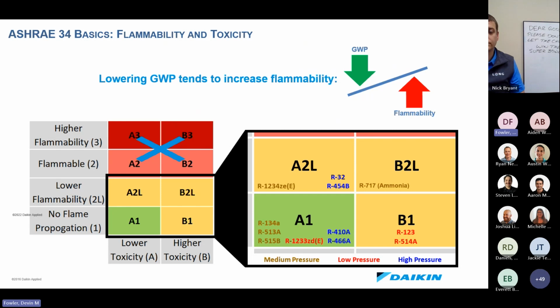I do understand that in Colorado, those refrigerants have been phased out due to GWP restrictions on the 1st of this year. What a lot of companies are transitioning to replace 410A is either going to be R32 or R454B. Those are A2L refrigerants, low flammability. What Daikin is doing to transition out of the R134A product are both R513A and R515B, no flame propagation and low toxicity refrigerants.